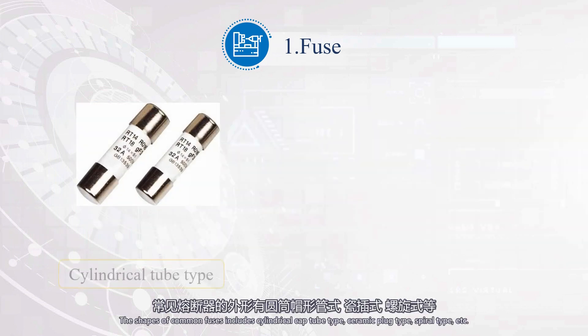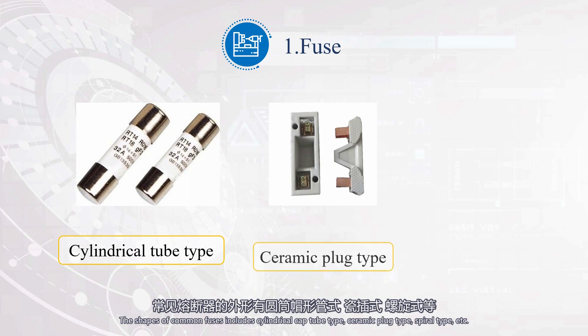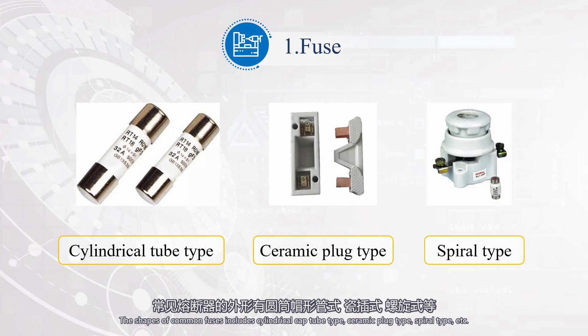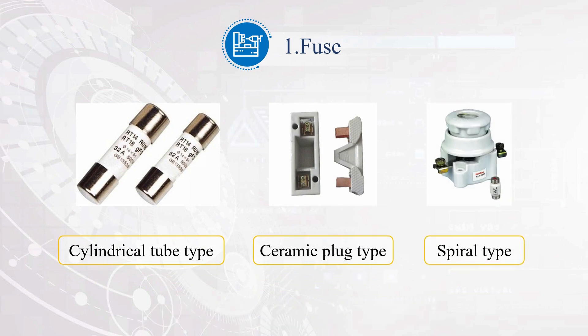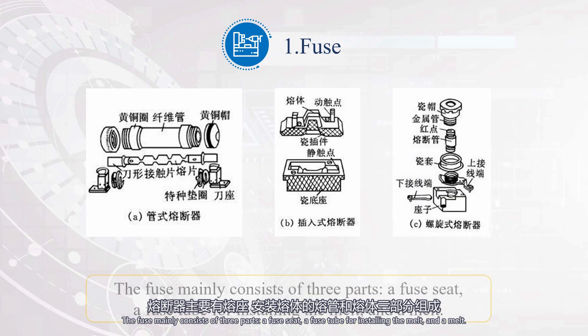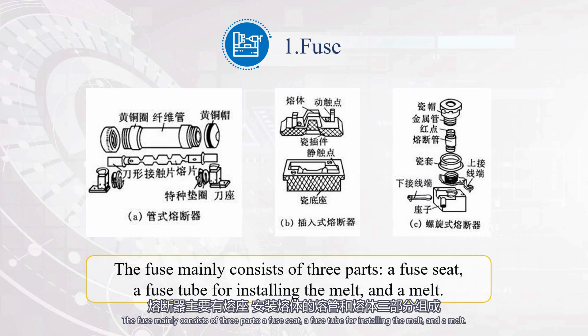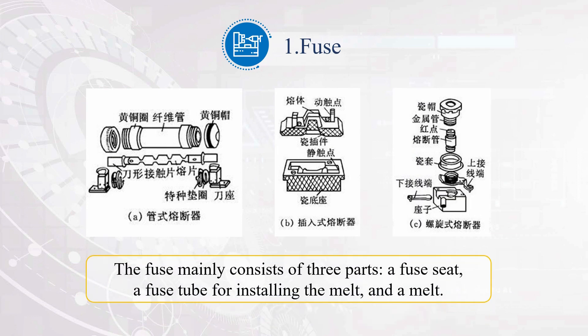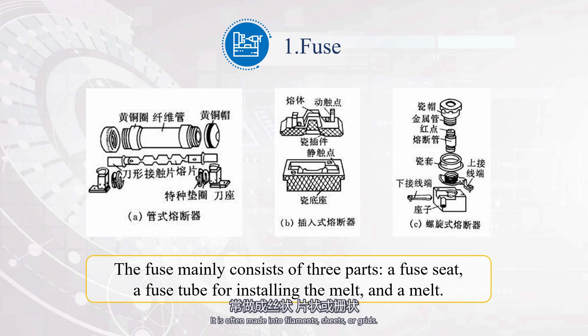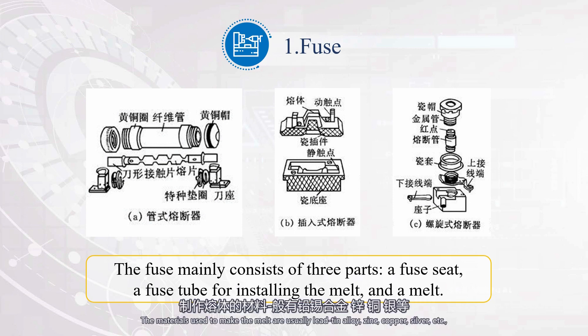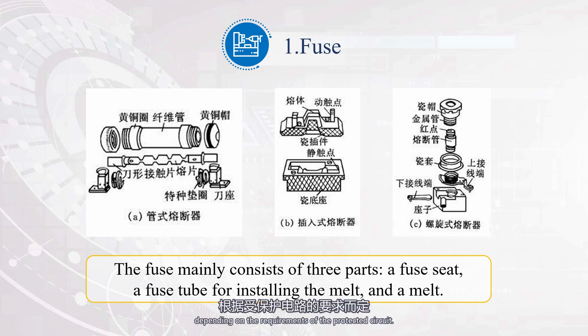The shapes of common fuses include cylindrical cap tube type, ceramic plug type, spiral type, etc. The fuse mainly consists of three parts: a fuse seat, a fuse tube for installing the melt, and a melt. The melt is the core of a fuse, often made into filaments, sheets, or grids. The materials used to make the melt are usually lead-tin alloy, zinc, copper, silver, etc., depending on the requirements of the protected circuit.